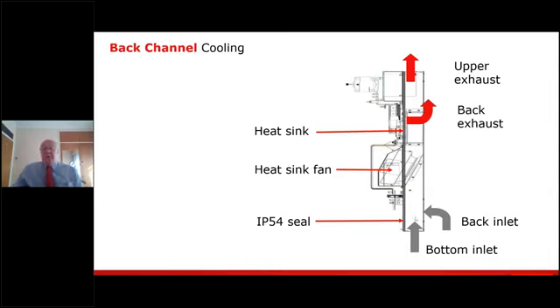So if we take a look, by means of back channel cooling, what we mean is we take the outside air either into the back of the drive or through the bottom, whichever way we go in, we block off the other. So if we take the outside air in through the back inlet, we block off the bottom inlet. This air then goes through the back channel and we exhaust it back into the outside atmosphere through the back of the drive or through the top of the drive. Again, whichever means we use to extract, we block off the other. So if we go through the back inlet and exhaust through the back exhaust, we would then block off the upper exhaust.